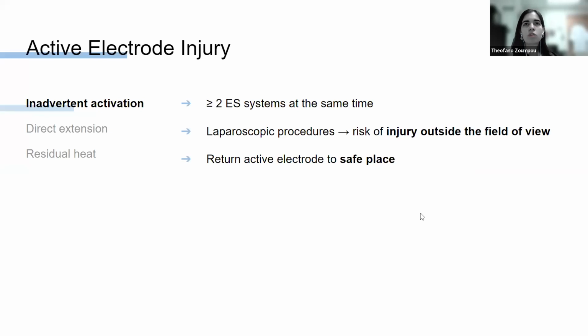The third mechanism that is important to be aware of in our clinical practice is injury related to the active electrode. And so inadvertent activation is a common cause of such injuries. And as the name implies, we have unintended, sometimes even unrecognized activation of our electrosurgical device. And this can happen with any type of device. The risk of inadvertent activation is high when we use two or more devices at the same time. And also, we need to be extra careful when performing laparoscopic procedures, because unintended activation can provoke injuries sometimes outside of the field of view, and they can go unnoticed, and this is a problem. One very simple yet very useful precaution we should follow is to return the instruments to a safe place when we don't use them, as we do when we replace the pencil in its holster, for example.